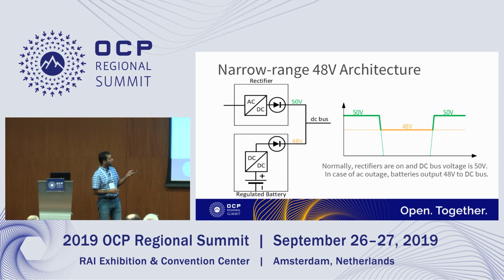So normally what you'd have is the rectifier at 50 volt, the battery at 48 volt, and two diodes connected. Normally the rectifier runs at 50 volt. When there's an outage or rectifier problem, the voltage goes to 48 volt, and then when it comes back it goes back to 50 volt. It's just the range of the voltage - very simply, as I'm presenting today, it's just 2 volts.